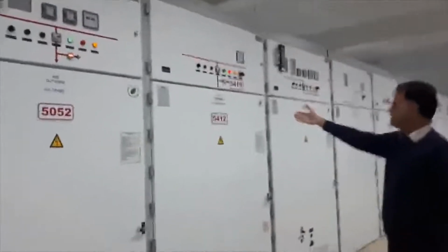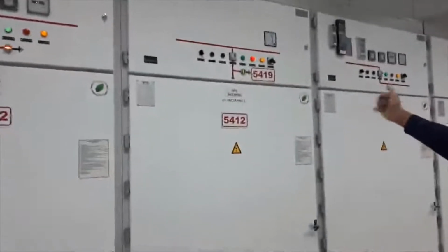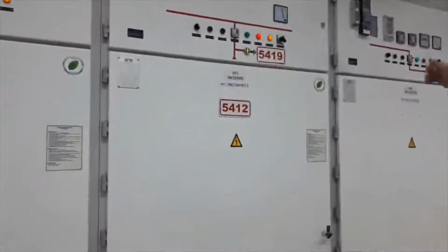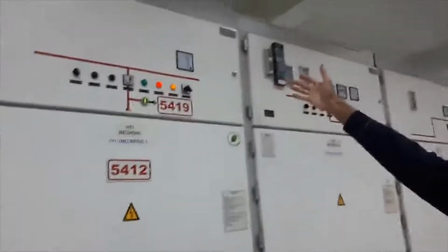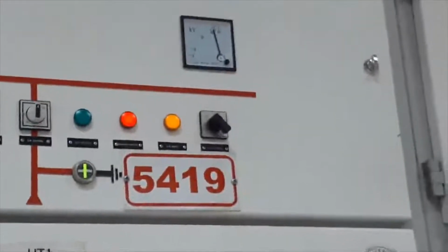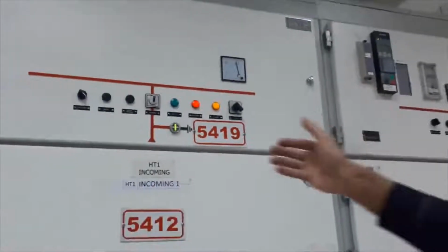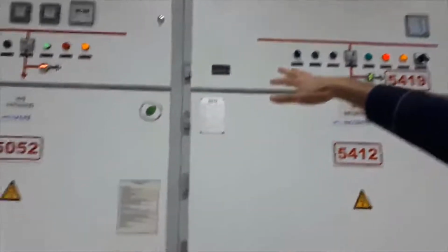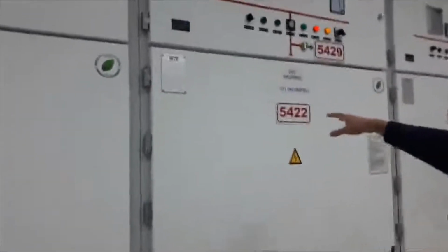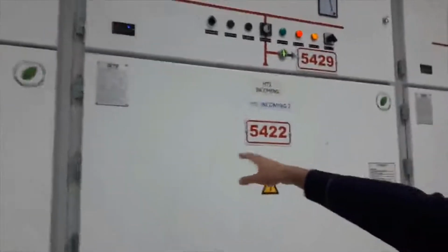This is our incoming cell, incoming 1. Its voltage, as you can see, is 33 kilovolts and it is now under load. The voltage is connected and you can see its indicator that shows we actually have voltage at the cable here. So this is our incoming 1. We also have incoming 2 here. In fact, we have two 33 kilovolt incomings.